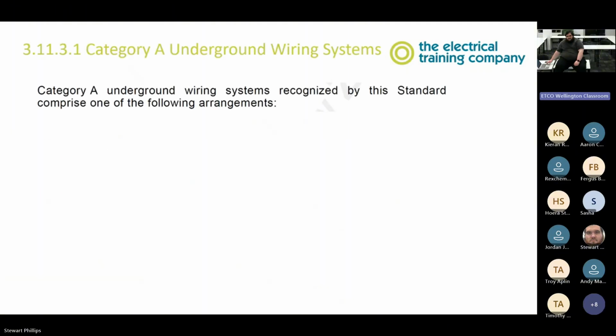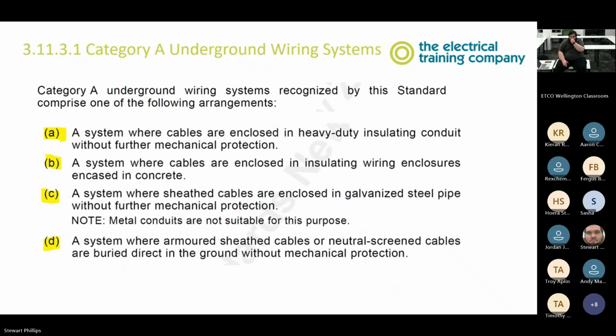Category A. So, systems recognized by the standard are the following arrangements. A system where cables are enclosed in heavy-duty insulating conduit. A system where cables are enclosed in insulating wire enclosures encased in concrete. A system where sheathed cables are enclosed in galvanized steel pipe without further mechanical protection.